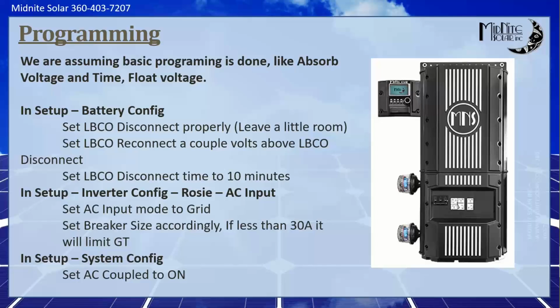What we found was the low battery cutout was set for 48, and the reconnect was set for 48.5. So with lithium batteries, when a load would come on, the voltage would dip to 48 for the time you can set as well, a delay time. And it would go past that time, so the Rosie would stop making AC, and then once the load is gone off the battery, it would bounce back to 48.5, and the Rosie would start right back up. So I recommend a couple volts because you really need to get some charge back in there before you start using that battery again. Set your disconnect time for about 10 minutes.